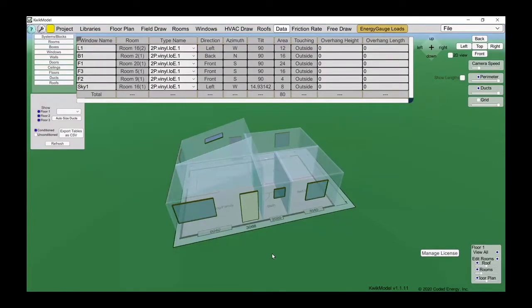But if it's a big door that has a little window in it, honestly, there's not really a good way to deal with those. For energy calculations, you would just model those areas separately. You would calculate the door area and then calculate the window area and call it a window with a little bit smaller door. And that's basically what I said by saying just draw the window off to the side. So the heat transfer through that window will get counted. It'll get calculated. It just looks kind of funny because the window's off to the side, but Connor's going to program it so that you can draw the window on top of the door so that it looks more normal.